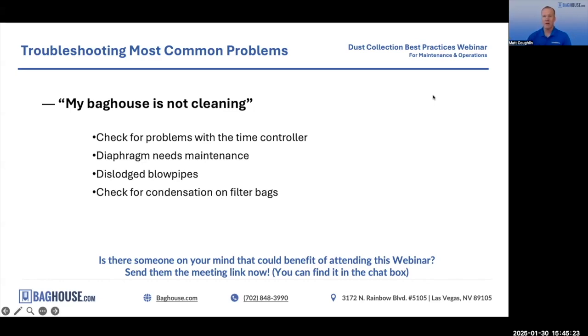Now, sometimes you have the whole system set up on clean on demand mode, which we recommend is the most efficient way. Basically, it means your system measures the differential pressure and it doesn't turn on until it reaches a set point, like 4 inches or whatever. So you might have to manipulate your DP tubes to get it to fire, but when you do that, it should activate the system. If it doesn't, again, it's one of those 3 issues. It's the timer board, it's your electrical connections or the solenoids, or it's the pulse valves themselves.